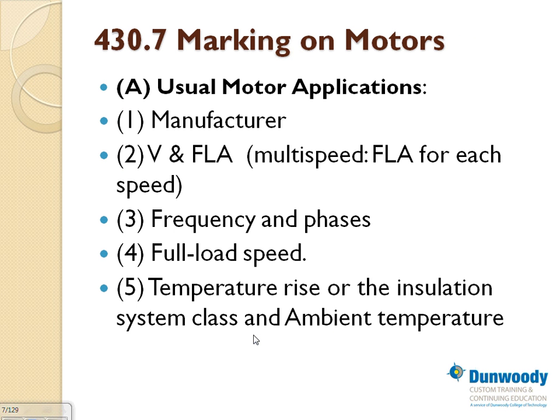Marking on motors by code. Now this is for manufacturers, not for us. We don't make motors, right? Manufacturers have to give you their name so we can sue them if something happens. You have to have their name, the voltage and the full load current. How about the frequency? And how about the three phase? You need to know if it's single phase, three phase, DC, AC, full load, speed, temperature, and the insulation class of that motor and the ambient temperature that this motor is working at.